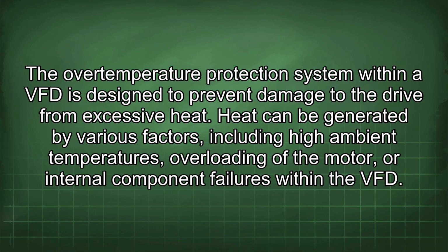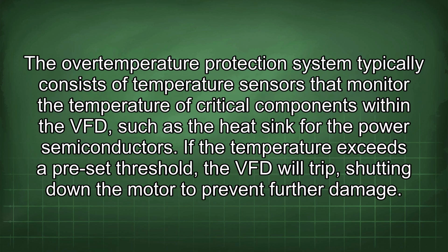The overtemperature protection system within a VFD is designed to prevent damage to the drive from excessive heat. Heat can be generated by various factors, including high ambient temperatures, overloading of the motor, or internal component failures within the VFD. The overtemperature protection system typically consists of temperature sensors that monitor the temperature of critical components within the VFD, such as the heatsink for the power semiconductors. If the temperature exceeds a preset threshold, the VFD will trip, shutting down the motor to prevent further damage.